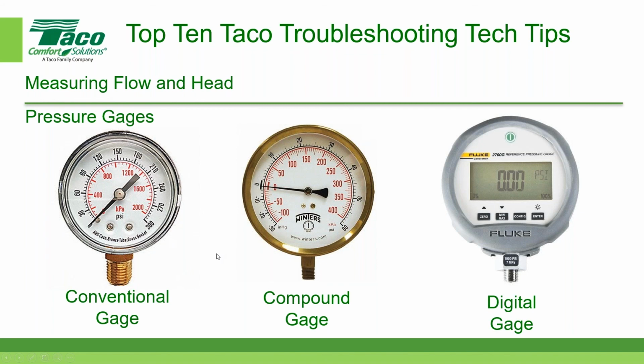So one of the challenges, especially in condenser water systems, actually came up about 6 months ago. We had a customer call and say, I'm getting zero pressure with the pump running on the suction side of the condenser water pump. And he showed me a photograph of the gauge, and I said, it looks like the needle on the gauge is pinned. He said, oh yeah, it's reading zero. I said, well, it's very rare that a gauge reads right on zero. It's probably less than that.